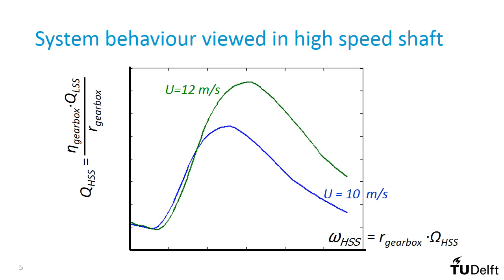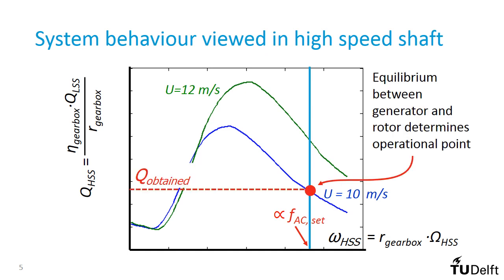Remember that the blue curve for 10 m/s wind speed was obtained by replacing the generator by a testing machine. Now that the generator is back, the generator takes the role of the testing machine. It sets the generator curve somewhere depending on the electrical frequency. The consequential torque in the high-speed shaft is where this curve crosses the blue curve. This is the point where the generator torque and rotor torque reach equilibrium in the high-speed shaft. If this generator was connected to the 50 Hz of the grid without a back-to-back converter, the operational point would always fall on this vertical line.